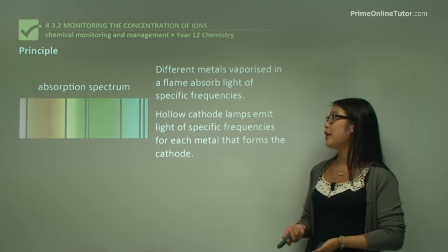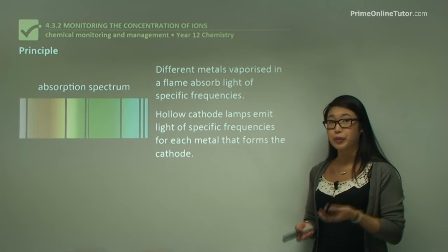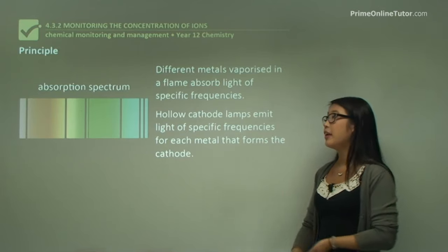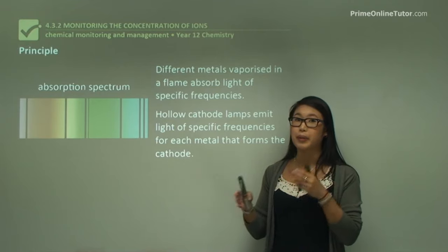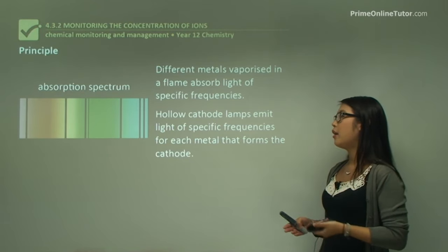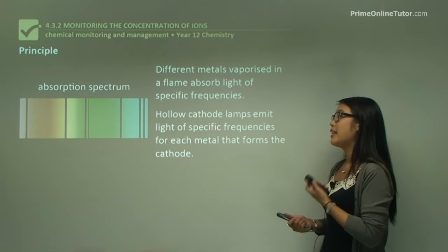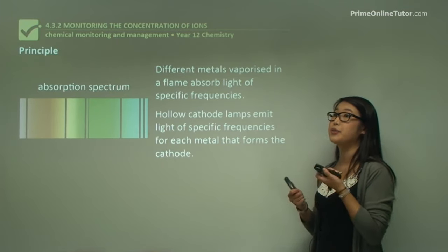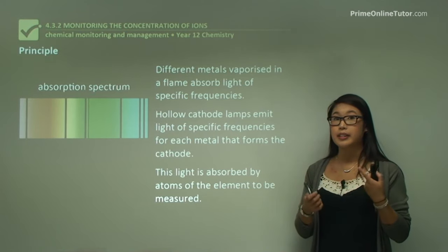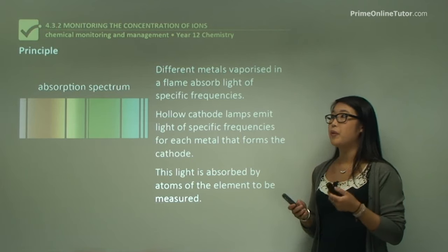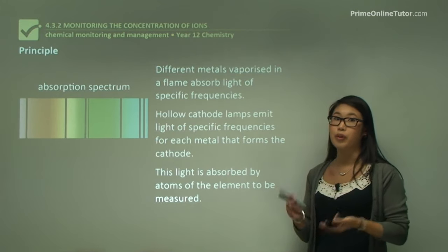Hollow cathode lamps emit light of specific frequencies, and it's specific for the metal we're looking for. If we're looking at one metal, it will have black bands at certain points, and another metal will have black bars at different spots. The hollow cathode lamp is specific for the metal ion we're looking for and is also made of that metal. Light is absorbed by atoms in the sample, and we can determine from the absorption spectrum what ions are present.